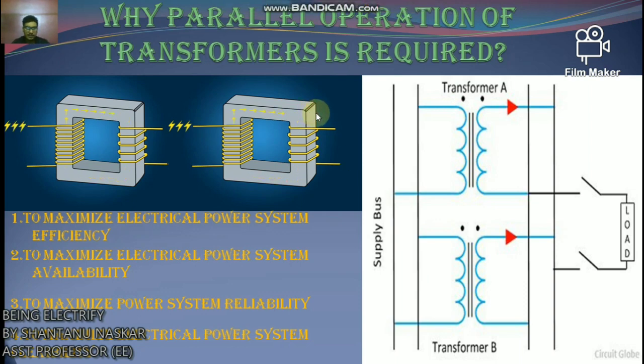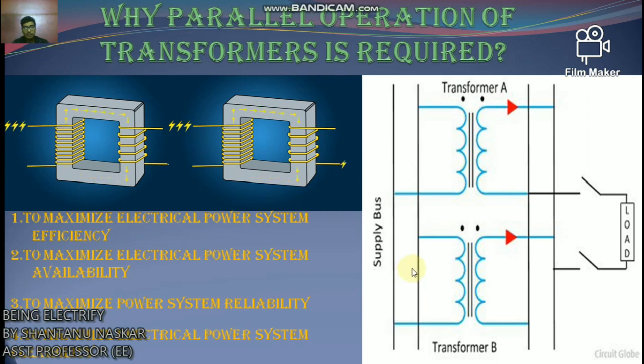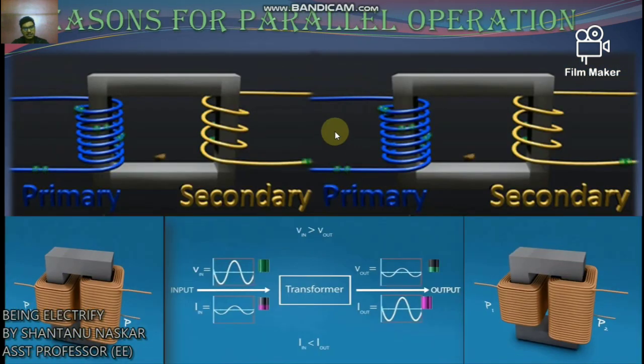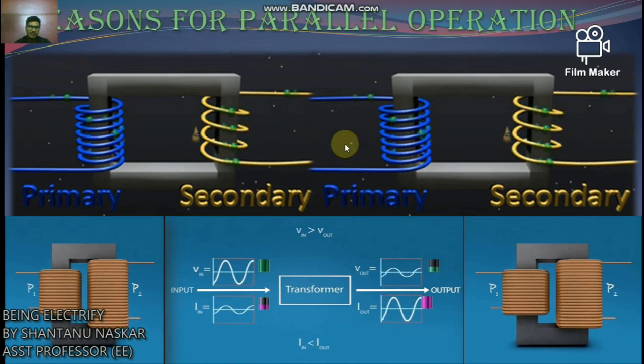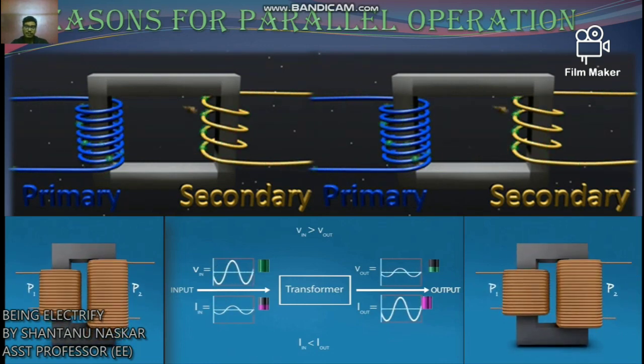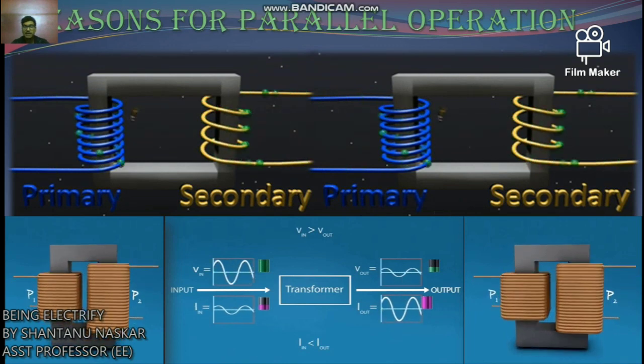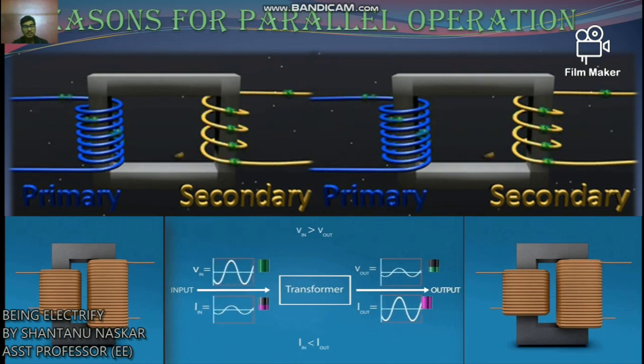A transformer is said to be in parallel operation when its primary winding is connected to a common voltage supply and its secondary winding is connected to a common load. The connection diagram for parallel operation is shown here. Parallel operation increases the efficiency and makes the system more flexible and reliable, but it increases the short-circuit current. It is also impractical and uneconomical to have a single large transformer for heavy loads, so connecting multiple transformers in parallel is the wise decision.